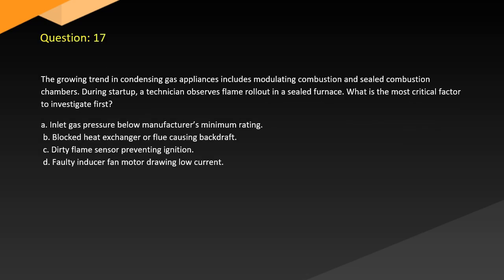Question 17. The growing trend in condensing gas appliances includes modulating combustion and sealed combustion chambers. During startup, a technician observes flame rollout in a sealed furnace. What is the most critical factor to investigate first? A. Inlet gas pressure below manufacturer's minimum rating. B. Blocked heat exchanger or flue causing backdraft. C. Dirty flame sensor preventing ignition. D. Faulty inducer fan motor drawing low current.